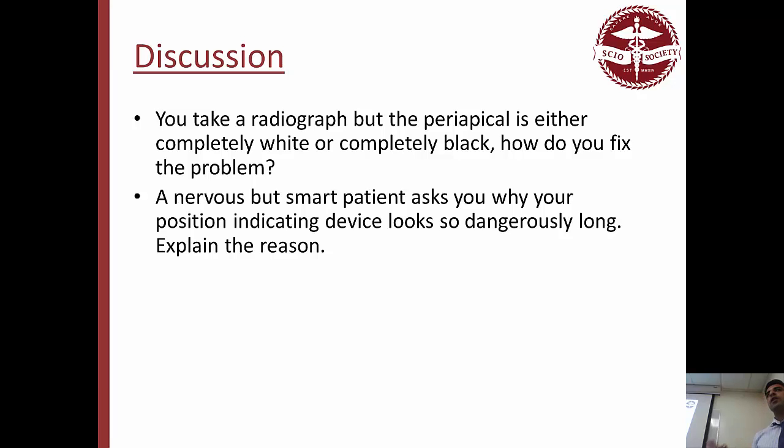Okay? What is one of the smart ways that machines can make the focal film distance longer without using a longer collimator? So do you guys remember that image in the class? So what they do is they place the tungsten target at the really back of the machine, so in the back of the head, so that way you have all of the head to collimate as well as the collimator. So instead of having it right in the front and the collimator being 16 inches long, you place the tungsten target in the back of the machine and the head itself is 8 inches long, then you only have to put an 8-inch collimator in front. So that's kind of one way to do it. And they have a really cool picture if you see it. You'll see it next time.